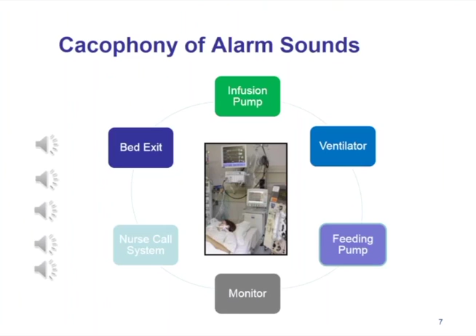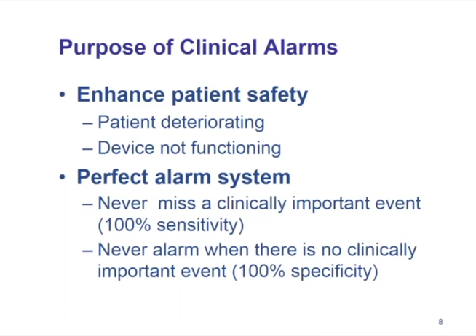Medical devices sound alarms 24 hours a day, and many times for non-actionable reasons. The purpose of clinical alarms is to enhance safety. They alert us when a patient's condition is deteriorating or when a device is not functioning properly. A perfect alarm system would never miss a clinically important event, meaning it would be 100% sensitive. It would also never alarm when there's no clinically important event, meaning it would be 100% specific. But by design, alarms are highly sensitive so they don't miss important events, and this high sensitivity is achieved at the expense of specificity. There are a lot of false alarms which can lead to alarm fatigue.